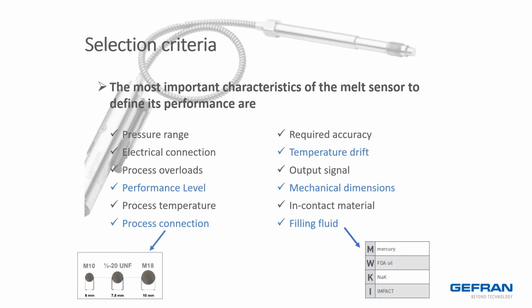There are quite a few variables that must be considered in order to have an optimal experience with such a delicate instrument. In particular, if you are not having that optimal experience with the sensor you use now and you need to choose an alternative, it is an opportunity to review all these conditions and make a more precise choice based on conditions that might be more specific to you and your application than to the original OEM design. For instance, mercury may no longer be allowed in the plant. Process temperatures may lead you to a different fill option too.